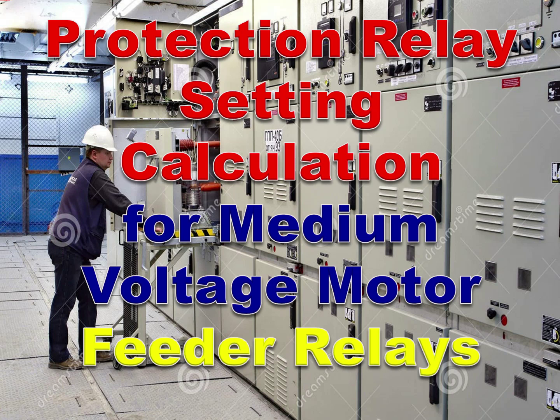We're going to tackle relay setting calculation for medium voltage motor feeder relays. This will be our single line diagram to where our MV motor is connected. This will be our multifunction relay. It is composed of protection relays at the same time with metering.